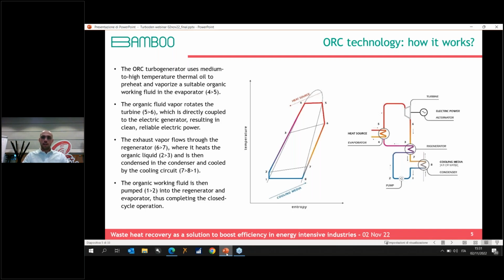So basically, the heat source is used to vaporize the working fluid at high pressure. This working fluid expands in the turbine, which extracts the useful work that is then converted into electricity by means of an electric generator. The vapor leaving the turbine still has some energy content that can be exploited within the regenerator component, which is basically internal heat recovery. Then we condensate our working fluid to bring it back to liquid form, restarting the cycle.